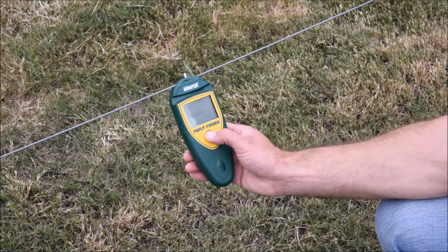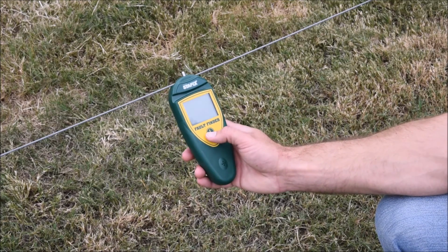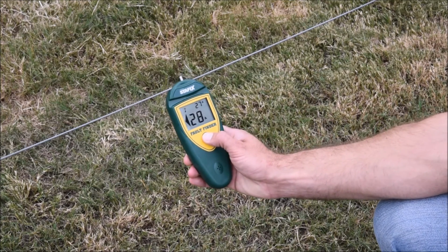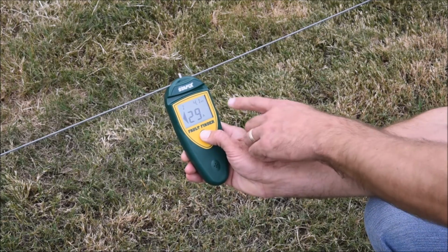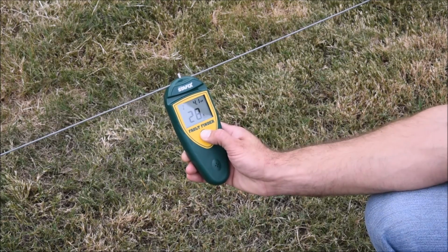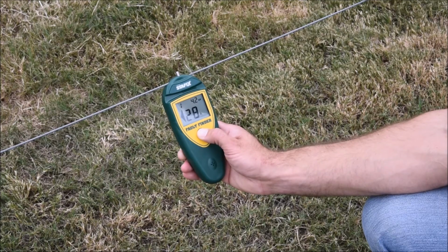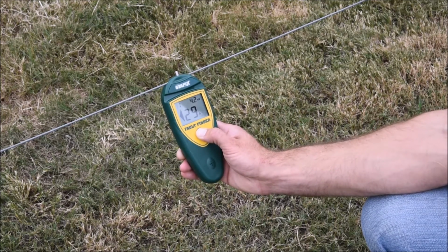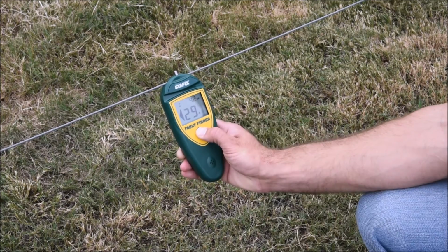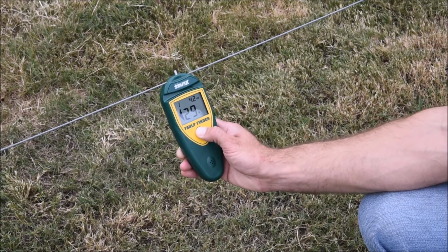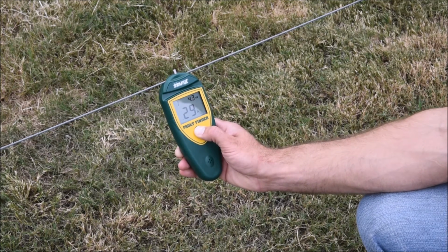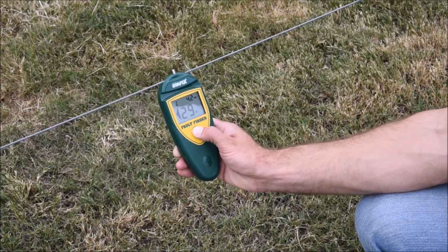So if we assume there's a fault on the fence, we can see by the voltage that the fence is reading less than it was at the start. There's also 29 amps of draw somewhere on the fence structure. There's a directional arrow that helps point us toward the problem.